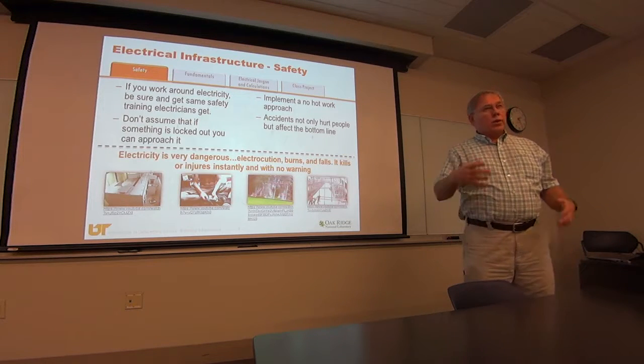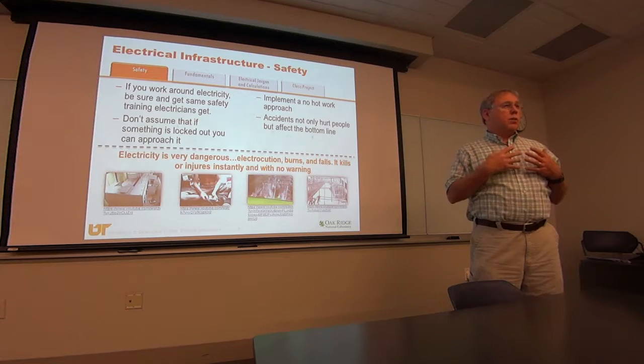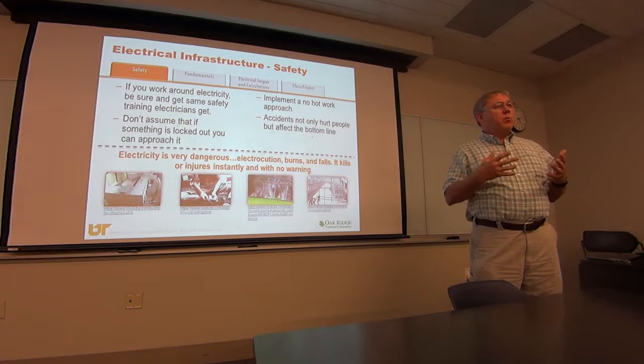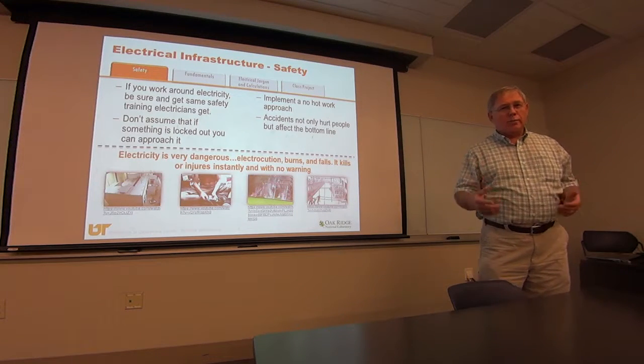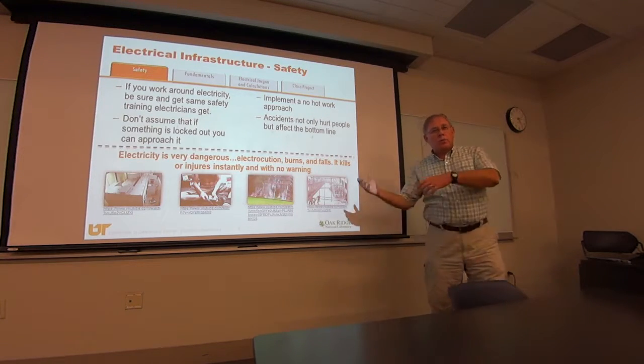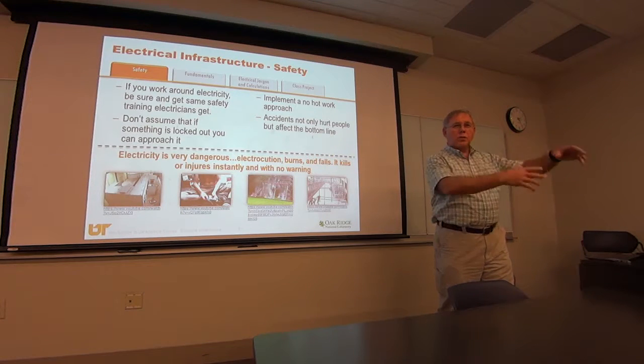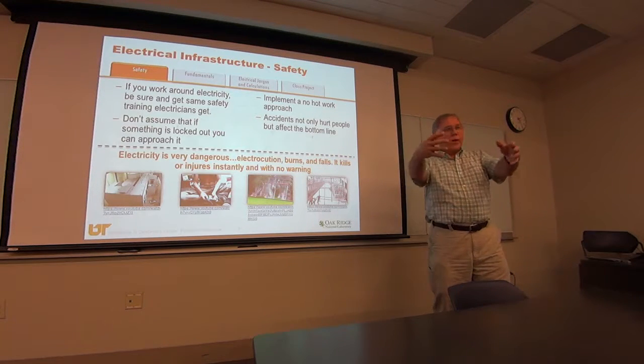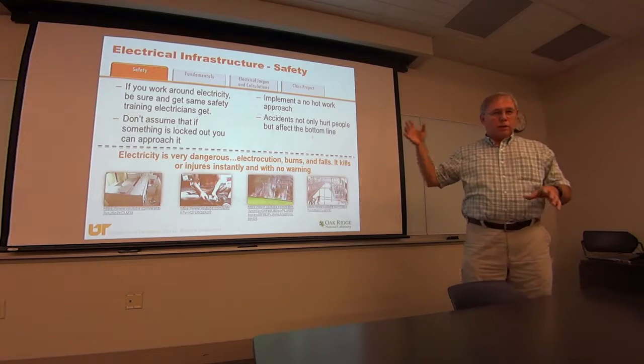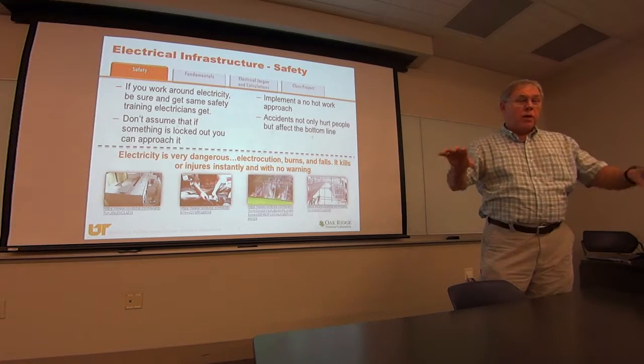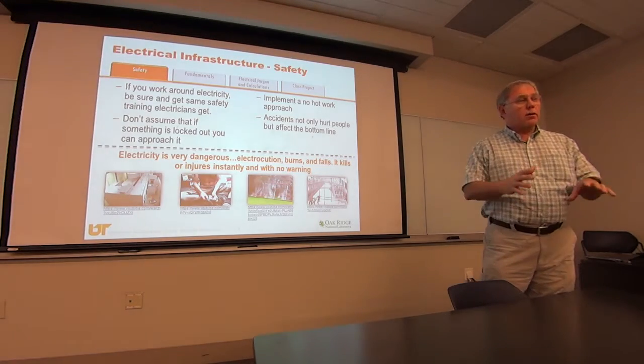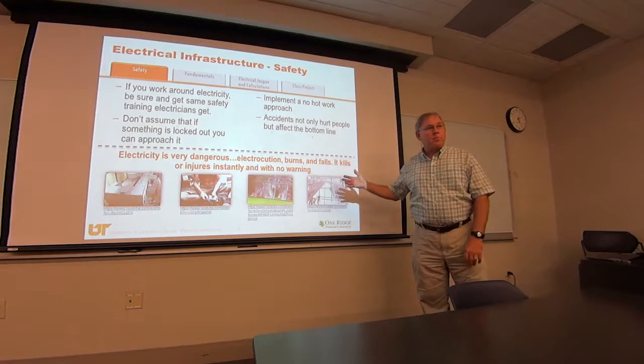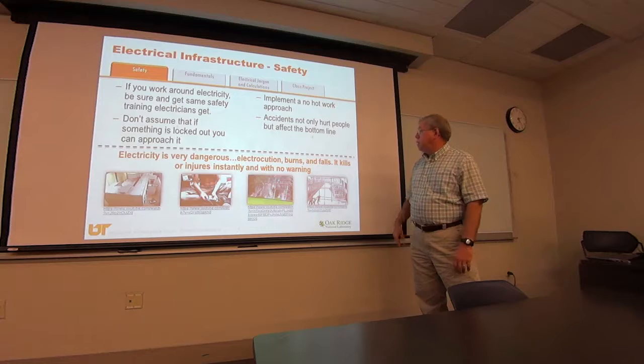So when that came down, we thought this is going to kill us because we can't get in there and make changes. But what it's forced us to do is think ahead. When we have gear down, we put spares out to boxes. We do things to think ahead so that when something happens, we just go out there, take a lock off a breaker, connect to the wires, take the lock off, and close it. We don't have to have outages, but you can live without that.